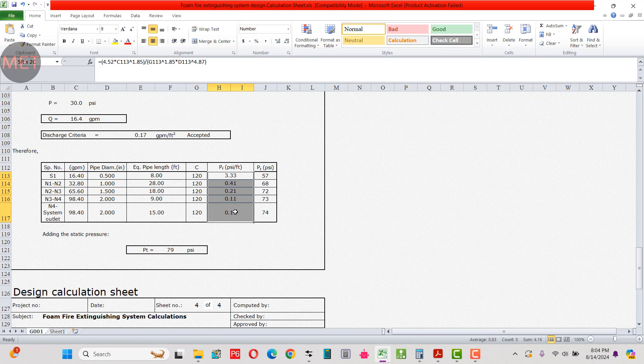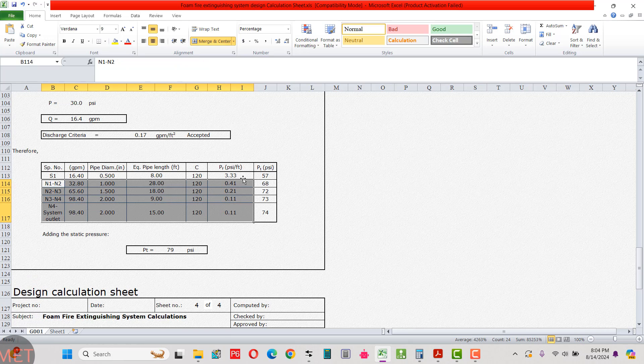You then calculate the cumulative total pressure loss across each pipe segment. For the first segment, start with the minimum nozzle pressure of 30 psi, then add pressure losses cumulatively for each subsequent pipe segment. After totaling all pipe segments, the cumulative pressure loss comes to 74 psi.